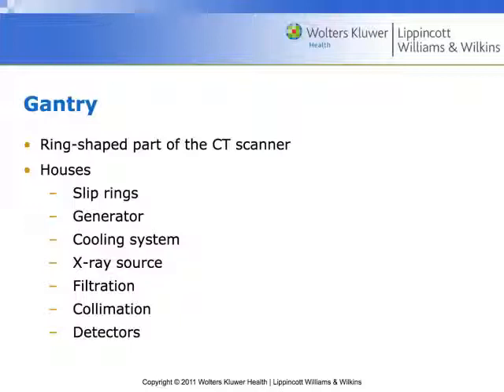We collimate both on the tube side and the detector side within a CT scanner. In nuclear medicine, something called edge packing occurs where isotope detection can be intensified at the edges of detectors — the same thing can happen with the CT detector array, and we'll talk about what we do to prevent that. When we talk about detectors, we're typically talking about the detector array; a detector is just a single element within that array.